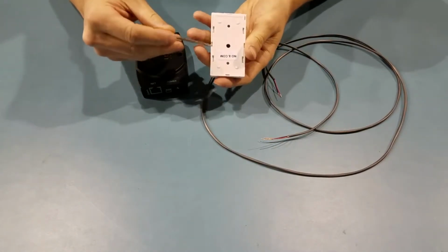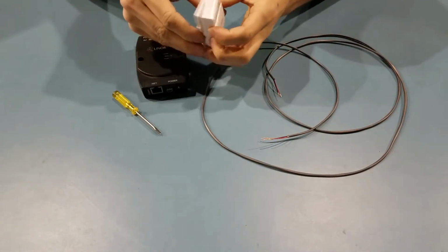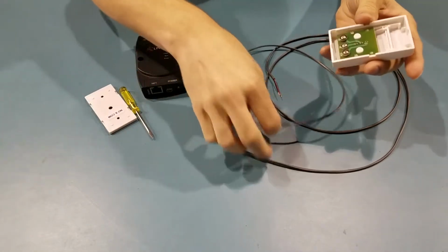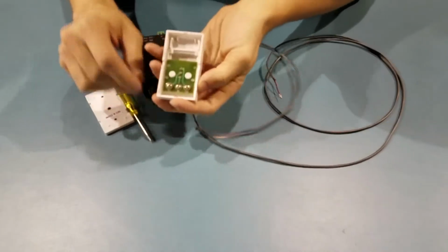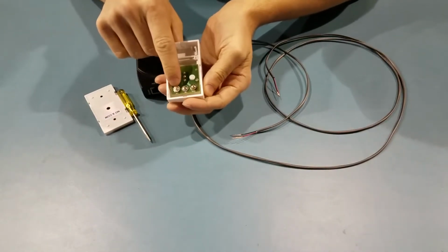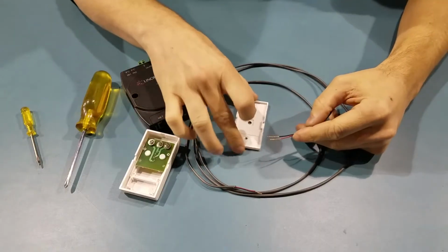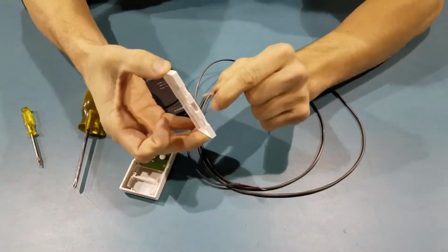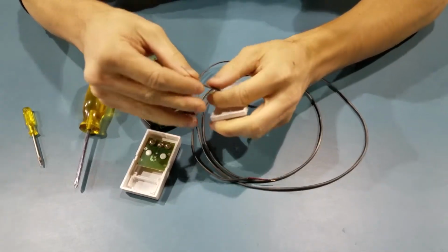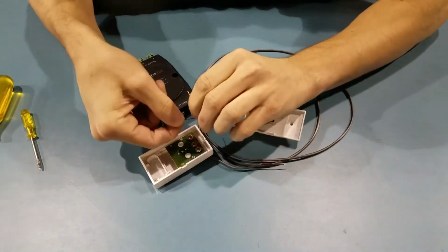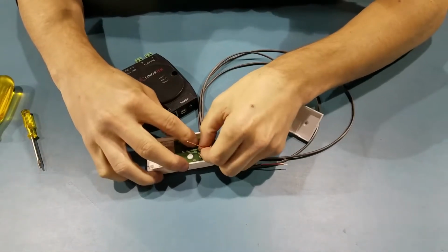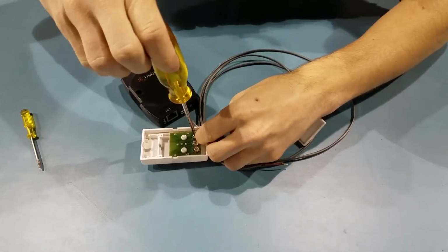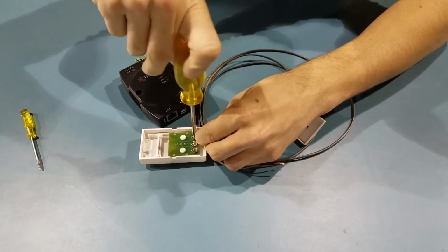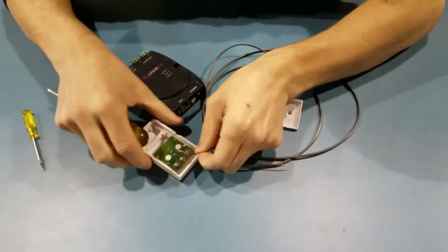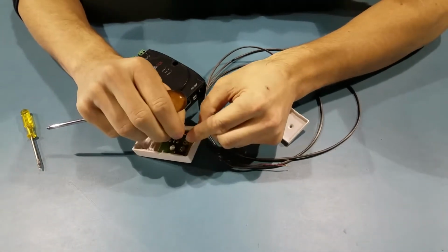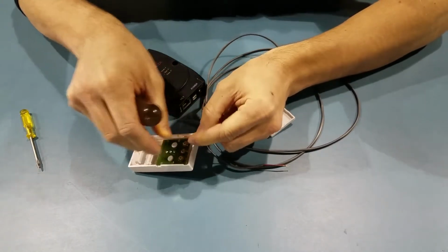To do this, you need to pop the back off the push button, and you'll see a common terminal and a normally open terminal. So first we need to push our wire through the back plate. We'll go and attach the black wire to the common terminal and screw it down tight. Pulling it to make sure it's a good connection, and do the same with our red wire on the normally open terminal.